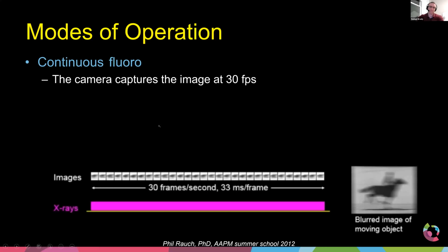All right. So when we deal with mag modes, it depends on the type of detector. There is definitely a dose change for the II mag modes, and there is a slight dose change for flat panel. But they're both doing that in order to keep the image quality, the signal to noise ratio, the same as it goes from low mag to high mag. The other way we operate a fluoro unit is the amount of images we acquire per second and then display them in real time.